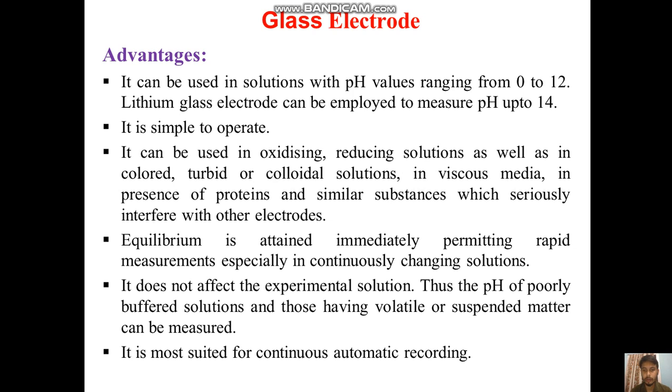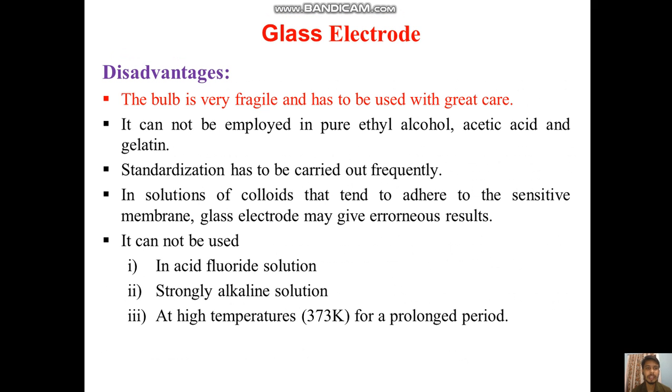It does not affect the experimental solution, so the pH of poorly buffered solutions and those having colloidal or suspended material can be measured. It is most suited for continuous automatic recording. Some disadvantages are also present: the bulb is very fragile and has to be used with great care. It cannot be employed in ethyl alcohol, acetic acid and gelatin. Standardization has to be carried out frequently, and in solutions of colloids that tend to adhere to the sensitive membrane, the glass electrode may give erroneous results.